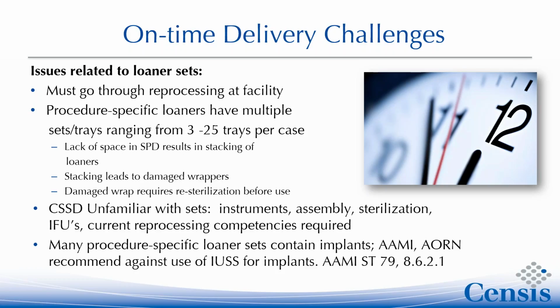And if a loaner set has an implant, regulatory guidelines recommend against immediate use steam sterilization. Unlike surgical instruments, implants by definition are going to be left in the patient. So to protect against surgical site infections, implants have a higher sterilization standard, and facilities want to adhere to the recommendation to avoid immediate use steam sterilization and run it through proper reprocessing.